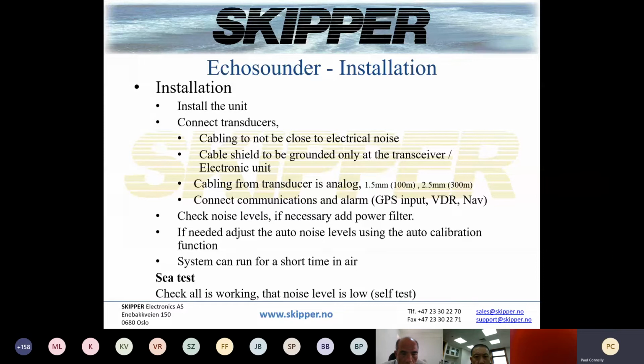Then, because you're on a new platform, there's an auto noise and auto calibration function - basically you press a button and it will find out what the noise level is and what the optimal signal to noise ratio is to confirm it's found the bottom. That helps the auto functions.